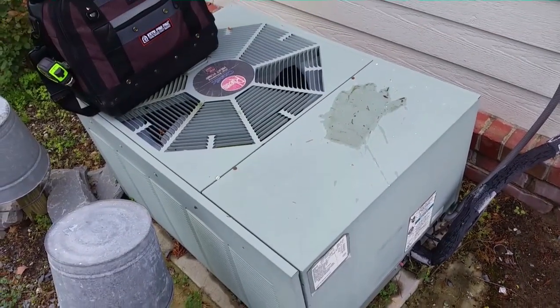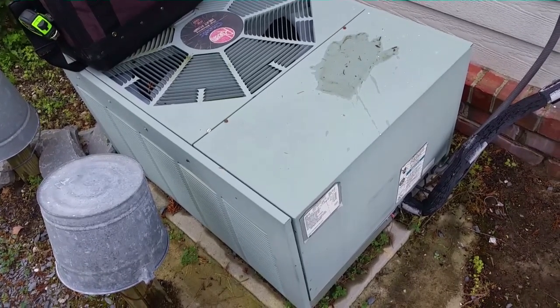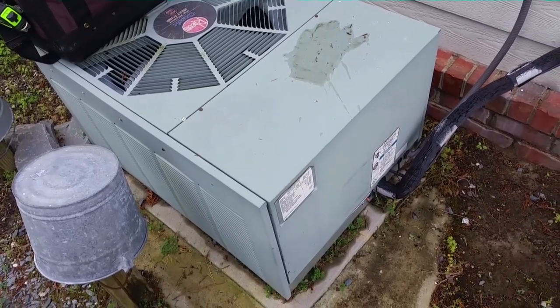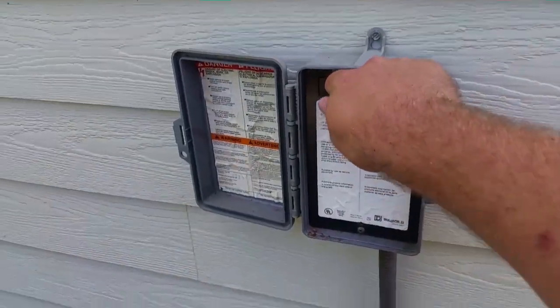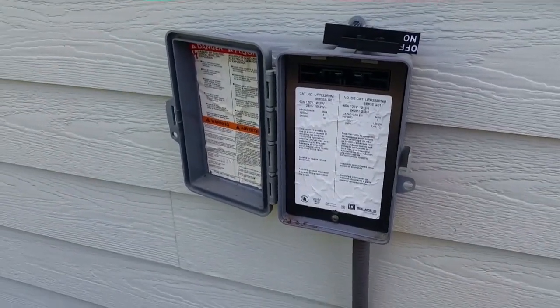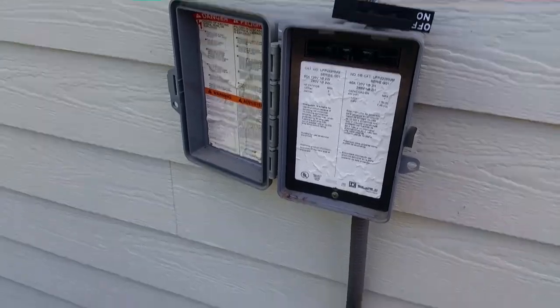I'm going to hook up the I-Connect to this machine — it's an old two-ton Rheem unit from the year 2000. We're going to look at how we connect the I-Connect, where we put our air probes to get all of our information. The first thing we do is pull the disconnect — safety first. Although if you didn't know to pull the disconnect when working on AC equipment, you should probably watch a different channel.